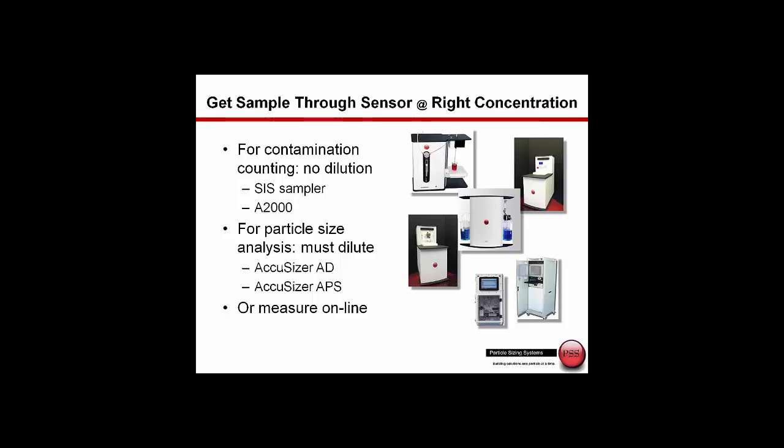So that's the sensor technology. We have a pulse height analyzer, which acts as the counter, but we also have different samplers in order to transport the sample through the sensor and also, if required, to do automatic dilution. The SIS sampler uses a syringe pump to draw the sample directly up through the sensor with no dilution. The A2000 system can have a single pump where we draw the sample directly through the sensor, or if we need to perform dilution, we can add an additional pump and draw a filtered diluent, mix that, and pass it through the sensor.